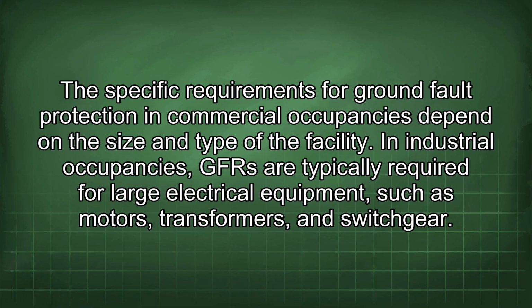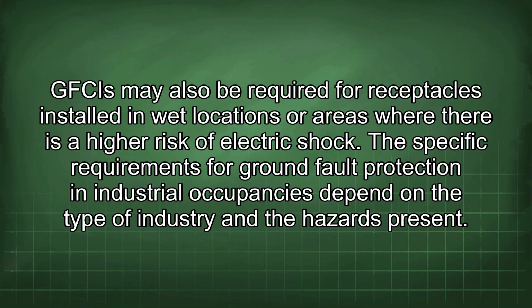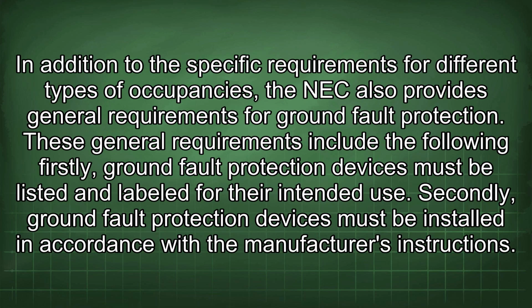In industrial occupancies, GFRs are typically required for large electrical equipment such as motors, transformers, and switchgear. GFCIs may also be required for receptacles installed in wet locations or areas where there is a higher risk of electric shock. The specific requirements for ground fault protection in industrial occupancies depend on the type of industry and the hazards present. In addition to the specific requirements for different types of occupancies, the NEC also provides general requirements for ground fault protection. These general requirements include the following.